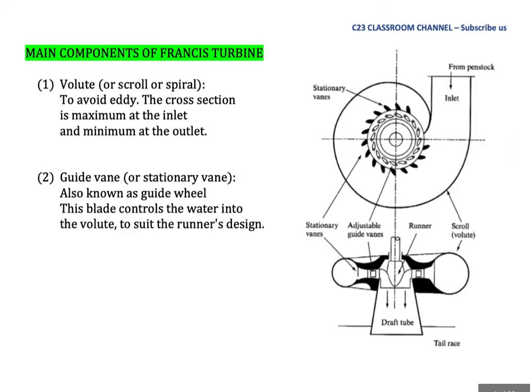This is the main component of Francis Turbine. Number one: Volute, also called scroll or spiral. It is located here. The volute in Francis Turbine is similar to the volute in a centrifugal pump. It was created to avoid eddy. The cross-sectional area is maximum at the inlet and minimum at the outlet.